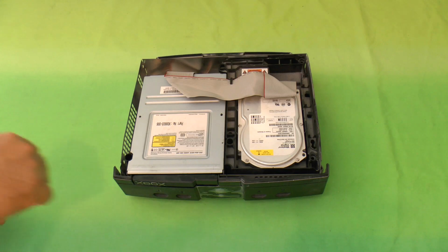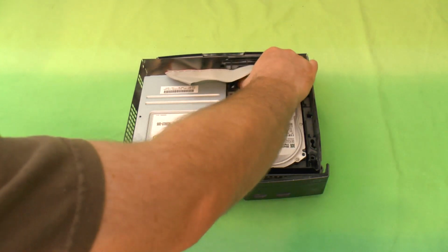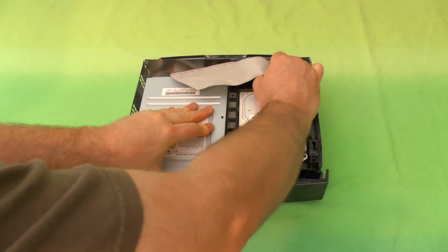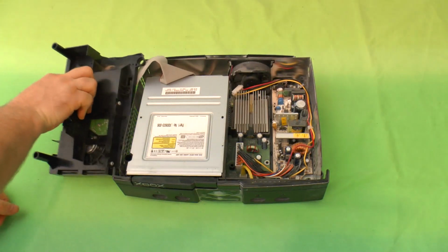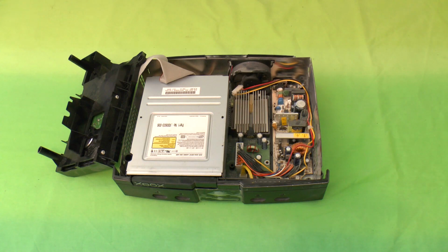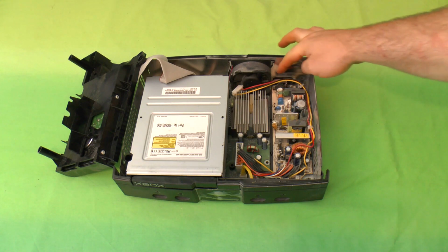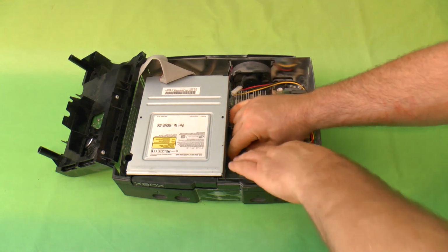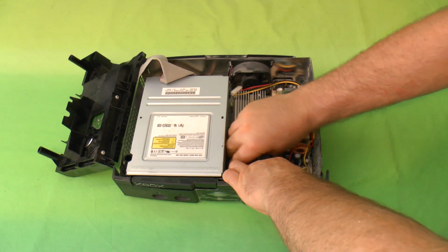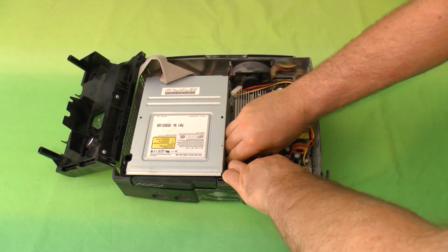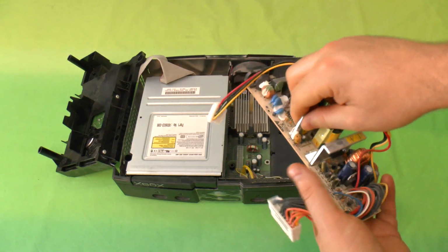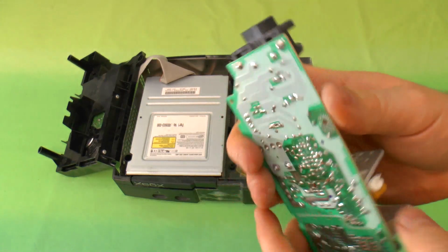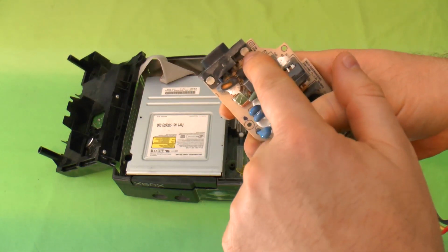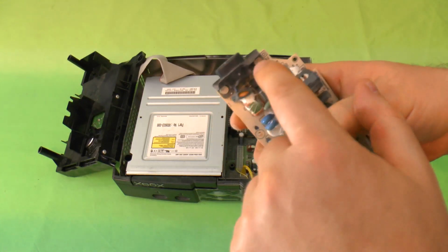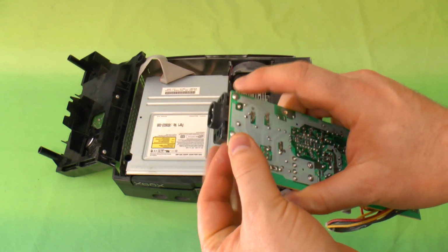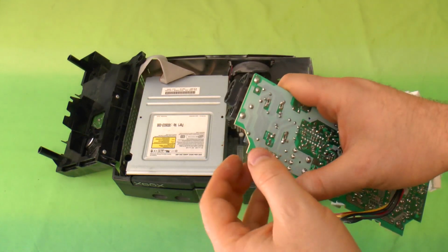Now, what the actual issue was, if I take a look in here at the power supply, is not the cable, but the connector. I shall just remove this power supply, and the issue you see on this one is that the connector is actually riveted down to the board, so it's got a nice secure connection, and there are the solder joints.